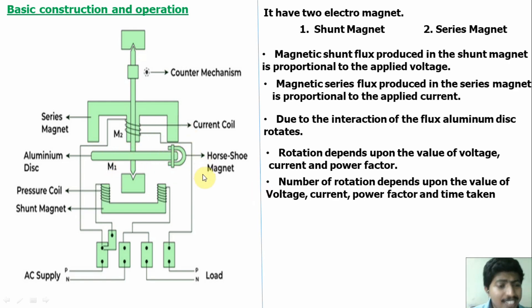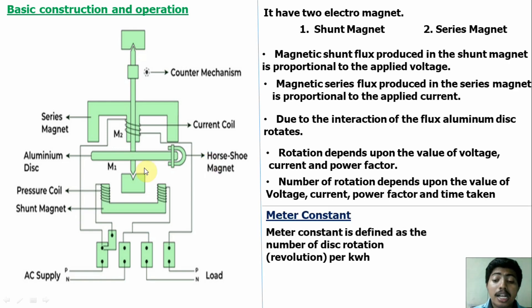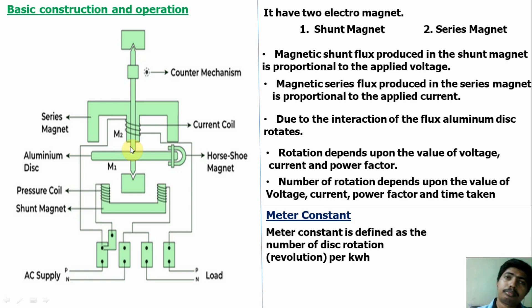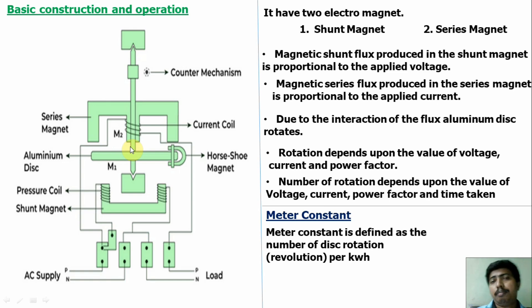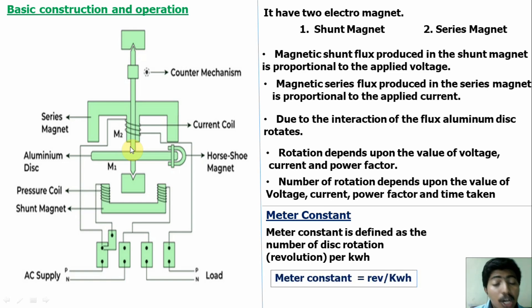When the meter consumes energy, the disc will rotate. Based on the number of rotations, we can calculate the energy value. Next, we will discuss the meter constant. Meter constant is defined as the number of revolutions per kilowatt hour. For example, if a meter takes 50 revolutions for one kilowatt hour, the meter constant is 50. Another meter may take 100 revolutions per kilowatt hour — that meter constant is 100. A meter constant is fixed for a particular meter but varies from meter to meter.